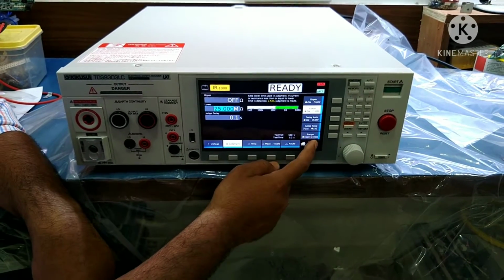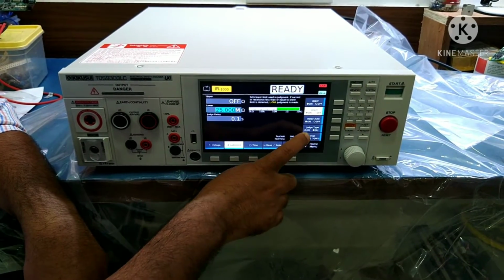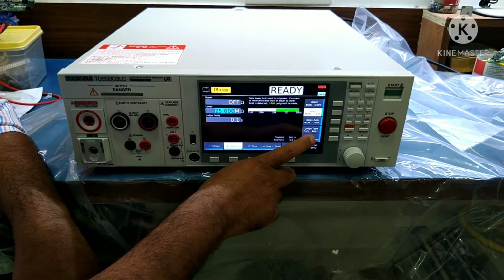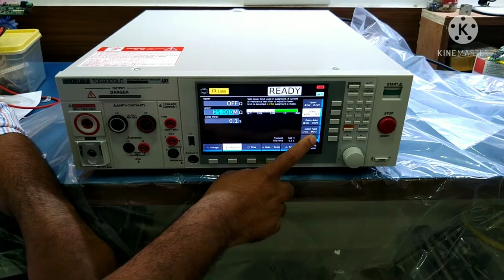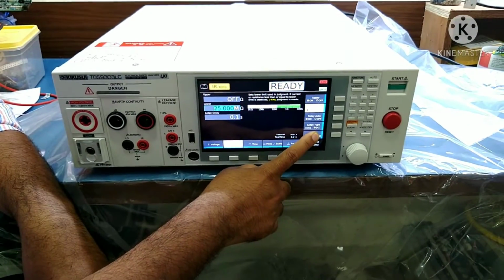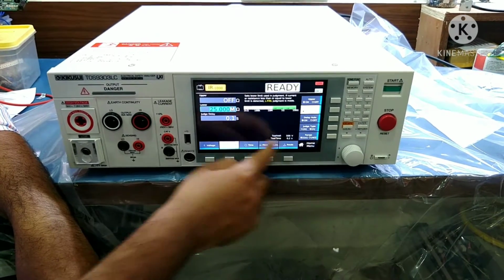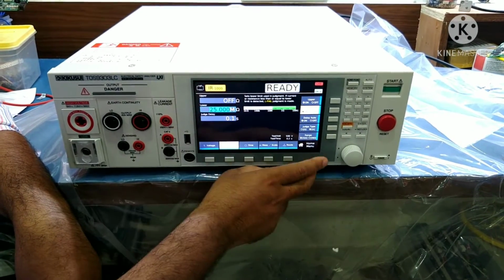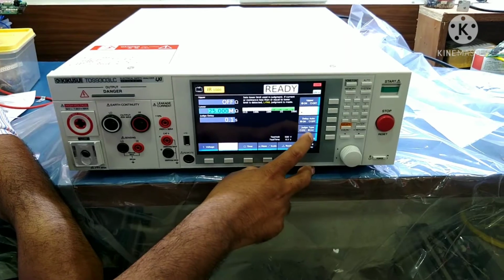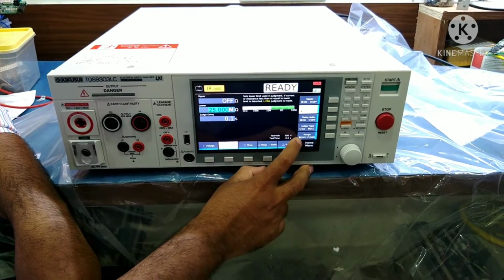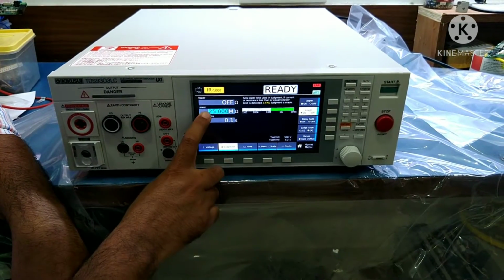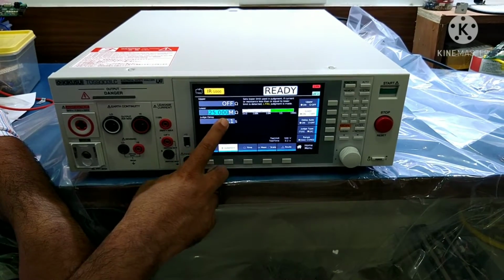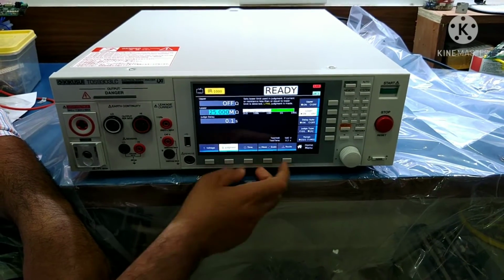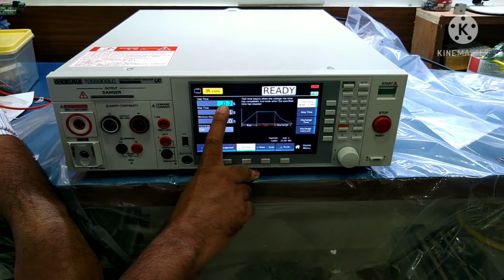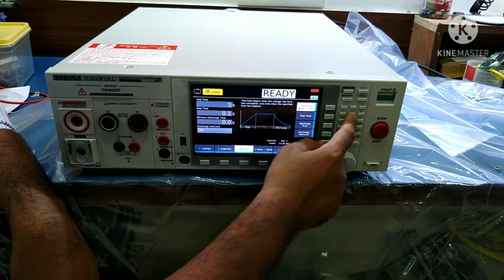All these settings you can set here, and you can also measure the ampere current that drops across the total circuitry. You can monitor it here by setting the ampere settings. This is the range, giga ohm, mega ohm. Right now I am setting it in mega ohm. If you require, you can set it in giga ohm also. Test time, what test time do you want to set? I am going to test for 5 seconds.